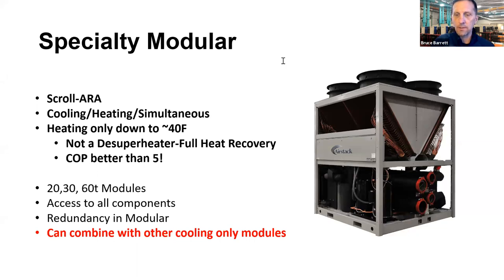What we found was certain owners had very small loops, no buffer, and that water would go out and come back and be immediately warmed, and they wanted the absolute fastest restart time. Certainly outside the norm for comfort cooling, there's ways to improve or lag that time. It's not a necessity or a requirement that they restart every 5 seconds.